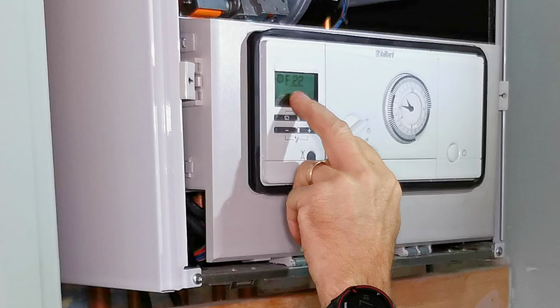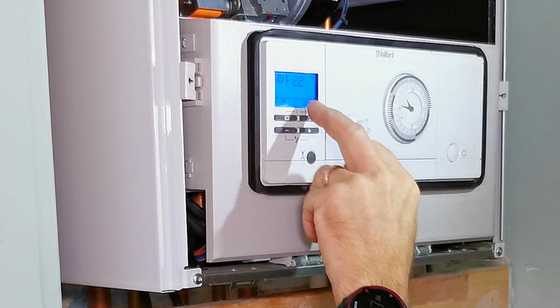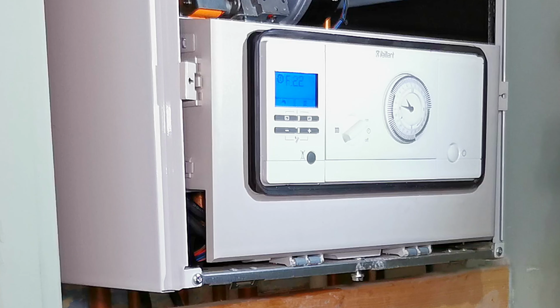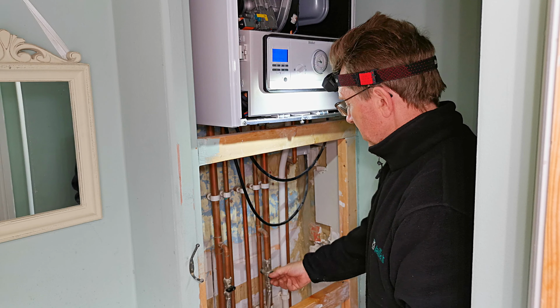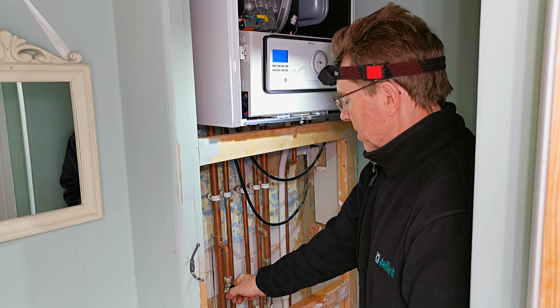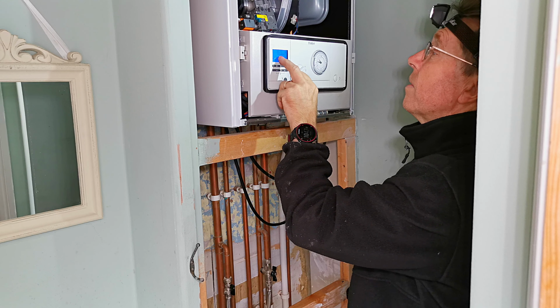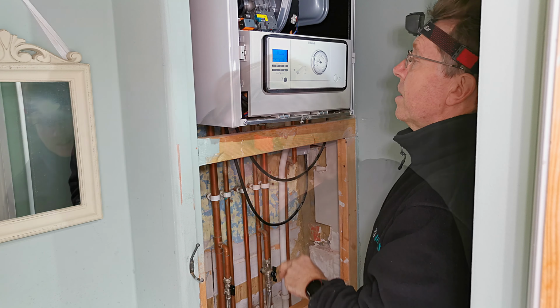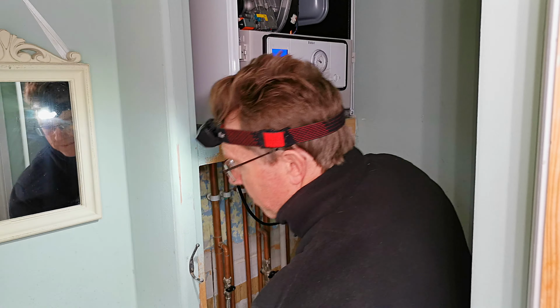Now I've turned the boiler back on, I've got F22 in the display as I would expect. So the pressure sensor is working fine on this boiler. I'm now going to open the filling loop and add a little bit of pressure to the system. Depending on your boiler depends on what filling loop you have. Now the pressure's not going up because I need to open the flow and return valves.